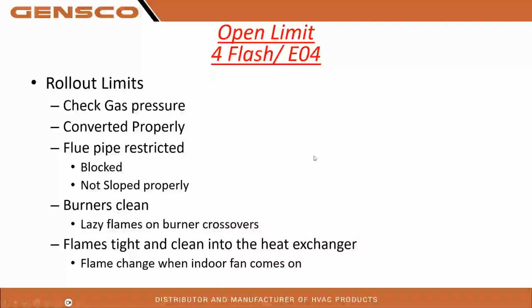So rollout limits, obviously we're going to have to check those too. That is part of that safety circuit. So we're going to look at our gas pressure. We're going to make sure it got converted properly if it was LP, right? We're also going to look for any kind of flue pipe restrictions that could cause rollout problems, right?